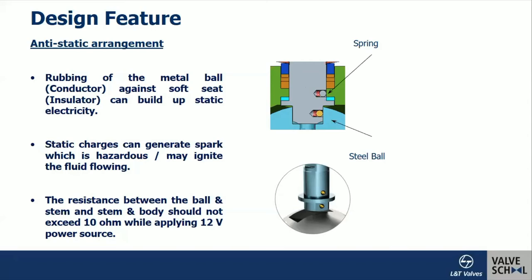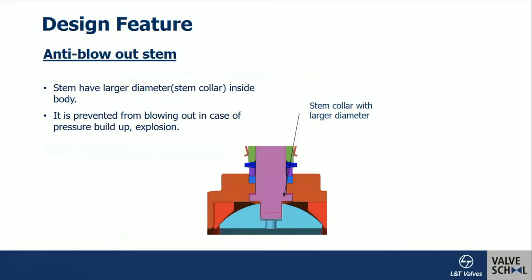The anti-static feature is tested using a device that ensures resistance is not more than 10 ohms when applying a 12V DC power source. Additionally, like many other valves, ball valves have an anti-blowout stem — the stem has a larger diameter profile such that even when internal pressure surges, the stem is prevented from blowing out of the body.